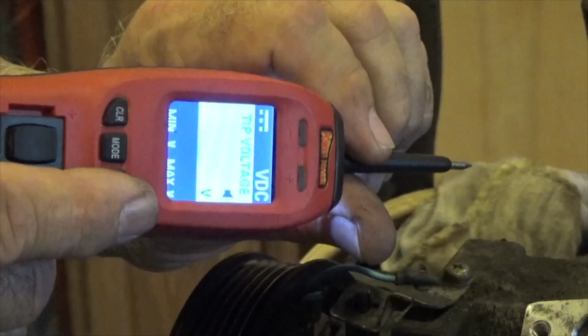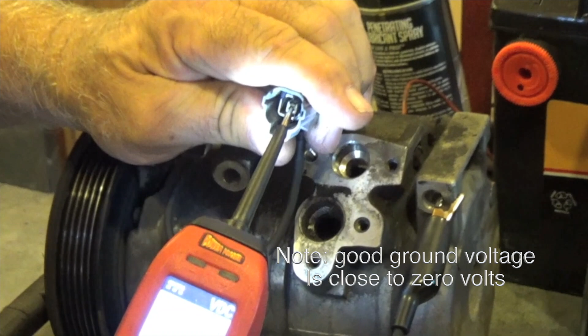So all I'm doing is tapping into the ground from this battery, and I'm grounding the case. Now if I continue, since the case is grounded, this screw goes through and is bolted to the case, so this screw should have ground, and it does. Your logic would tell you that if that goes through there and into here, I should have ground on this wire. So now I'm going to tap into that, and you'll notice I have no voltage, no green light. The important thing is there's no voltage at all, so that's an open circuit.